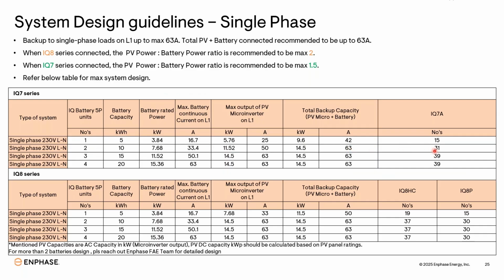So the maximum inverters you can connect in that phase is 31, in all three phases, 31 in R, 31 in Y, 31 in B. So in total you can connect 93 inverters maximum. Same with 3, same with 4. So you see we have limited the current to 63 amperes. 15.36 multiplied by 1.5 will be more, but we cannot exceed the 14.5 limit. So that's why we will limit it here, the PV limit. So 39, 39 we have for 3 and 4 and further on.